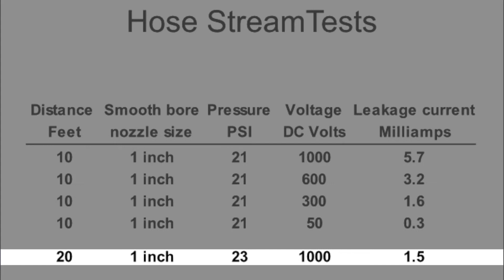At 20 feet away, there was no perceptible current even at 1,000 volts. So if you're only using a smoothbore nozzle, the recommendation is to maintain at least 20 feet away for up to 1,000 volts. However, since most departments do have combination nozzles, once the nozzle pattern was opened to at least 10 degrees, the tests found you could get less than 5 feet away from 1,000 volts. This was very helpful information for firefighters to understand how close they can actually get to an energized PV system and attempt to knock down the fire.